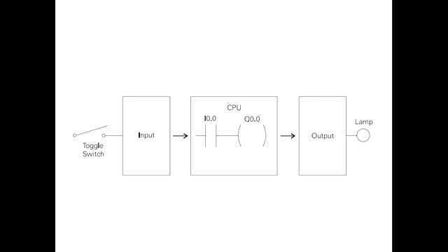Status functions. After a program has been loaded and is running in the PLC, the actual status of ladder elements can be monitored using STEP 7-Micro/WIN32 software. The standard method of showing a ladder element is by indicating the circuit condition it produces when the device is in the de-energized or non-operated state. In the following illustration, input 1, I0.0, is programmed as a normally open, NO, contact. In this condition, power will not flow through the contacts to the output, Q0.0.